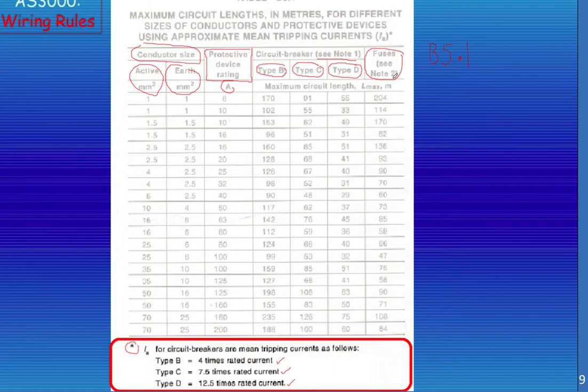So this table tells us the maximum length we can run in meters for our active and for our earth, depending on the current rating of the circuit breaker and the distance that we need to actually travel. So when they say circuit length, they actually mean the length of the cable.